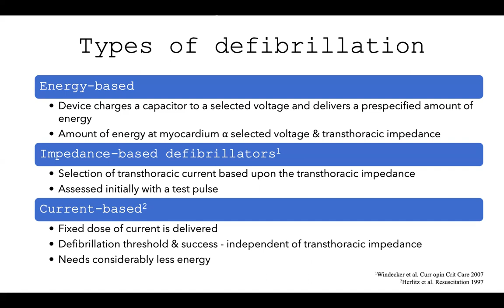What they usually do is assess the transthoracic impedance by giving a test pulse. The third is called the current-based defibrillator, where a fixed dose of current is delivered. The defibrillation threshold and the success in this case are independent of the transthoracic impedance, and it also needs considerably less energy to achieve its target.